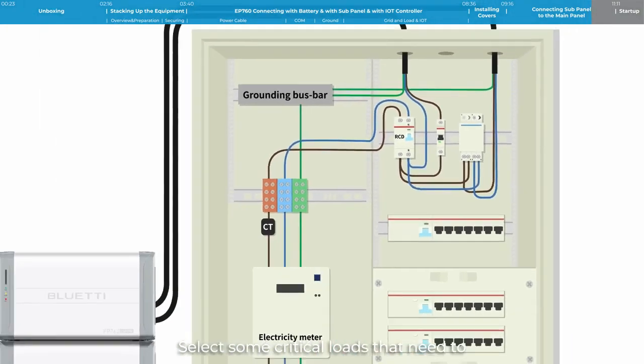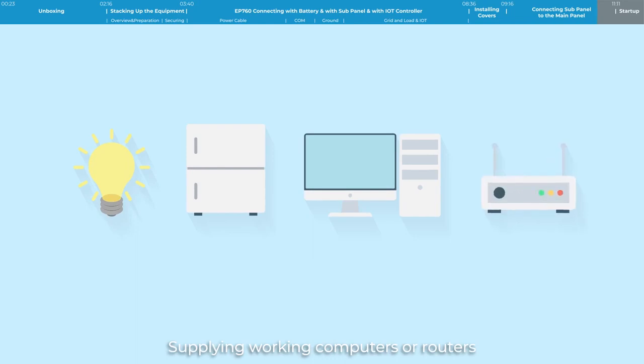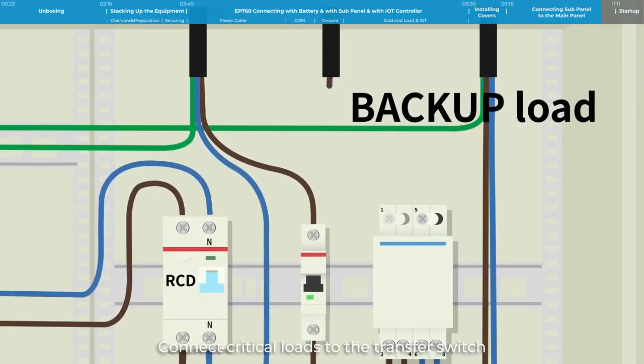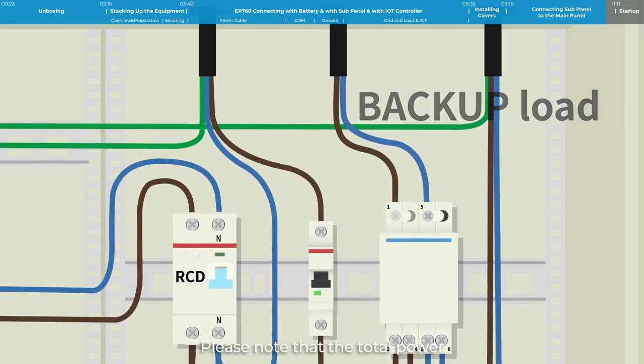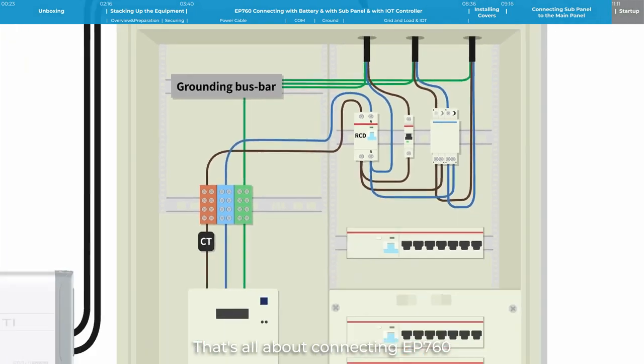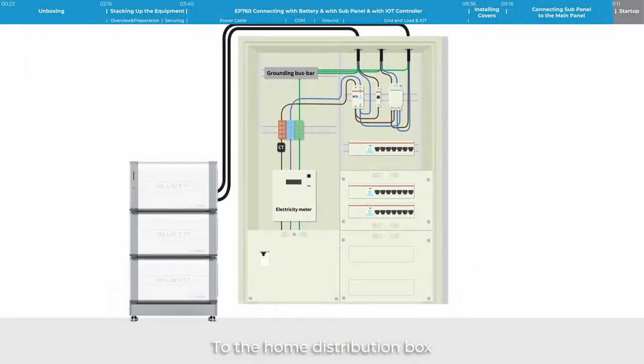Select some critical loads that need to operate during mains failure, e.g., lights, refrigerators, circuits supplying working computers or routers. Connect critical loads to the transfer switch, L to pin 1, N to pin 5. Please note that the total power of essential loads is less than 7,600W. That's all about connecting EP760 to the home distribution box.